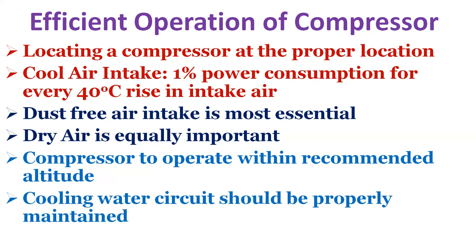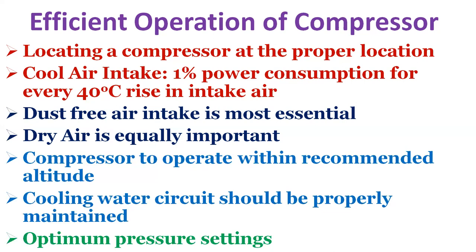Dust accumulated in filters should be removed regularly and filters replaced when needed; manometers or pressure switches warn of high differential pressure across filters. Dry air is equally important — moisture can convert to water during compression and damage compressor parts. Compressors must be operated within the altitude recommended by the manufacturer. The cooling water circuit should be properly maintained, as compression raises temperature and intercoolers require correct water quality and quantity. Finally, optimum pressure settings should be configured for load and unload operations.